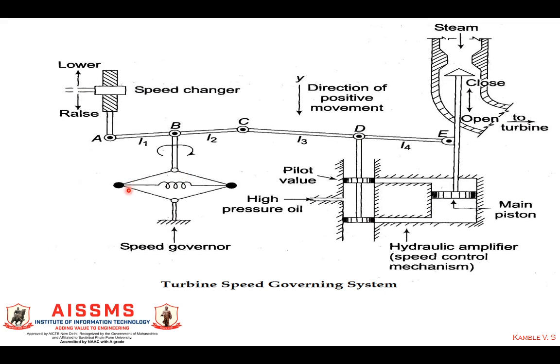In the opposite case, suppose the speed of the generator decreases — the flyball will move in the inward direction. When it moves inward, B moves upward, C downward, D upward, and E downward. When D moves upward, high-pressure oil flows in that direction, moving the main piston downward. When the main piston moves downward, the steam valve opening is increased, so the rate of flow of steam to the turbine is increased. The turbine rotates at a higher speed, the generator rotates at a higher speed, and it increases the active power — that is, it controls active power as well as frequency.